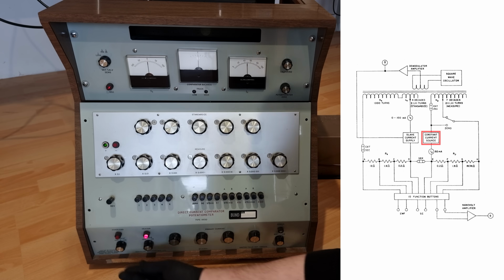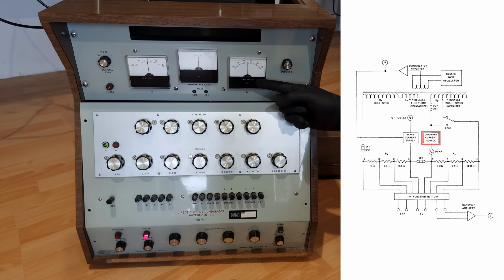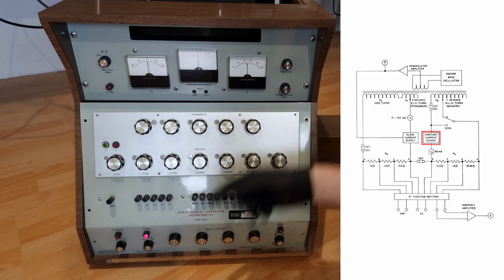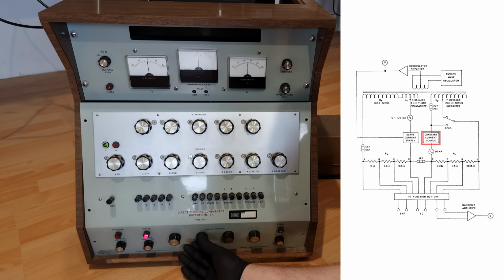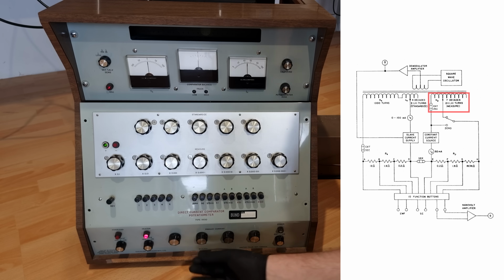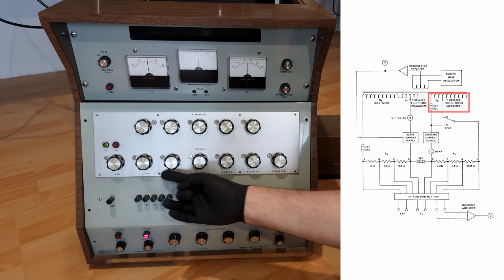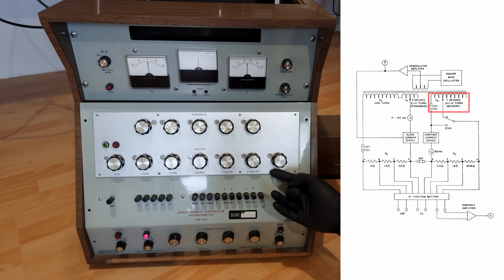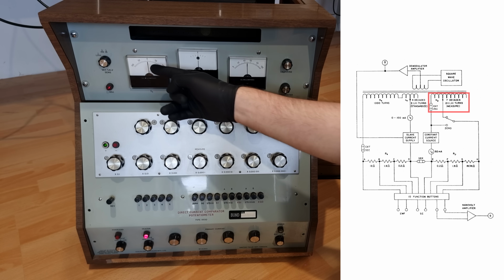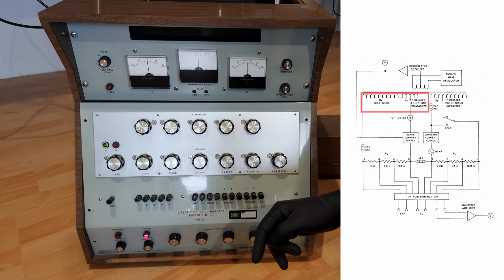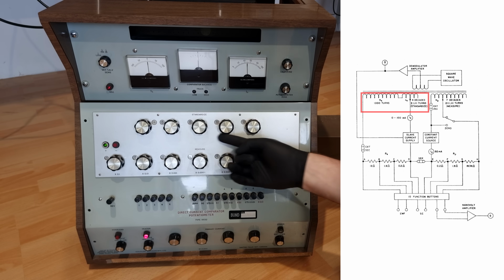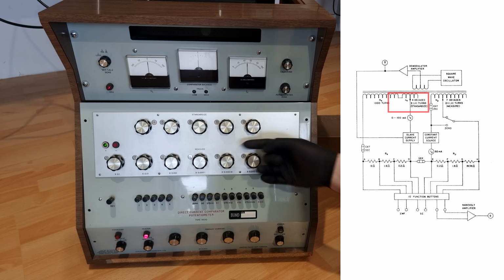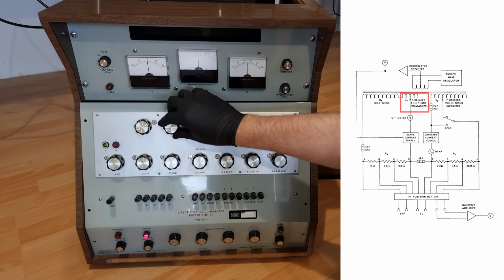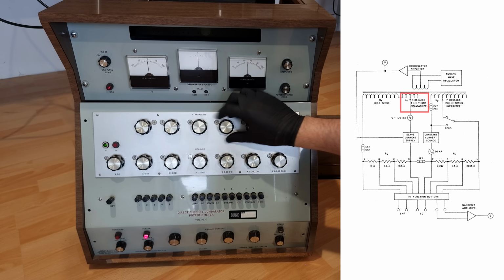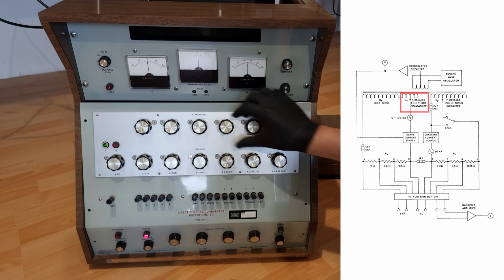Constant primary current source. This can be considered 50 mA. The fine adjustments in the bottom row are only for some special scenarios. This primary current goes through measure number of windings, none, so the comparator is balanced with no secondary current. The number of secondary windings is 1000 plus standardize, so just 1000 at this setting.